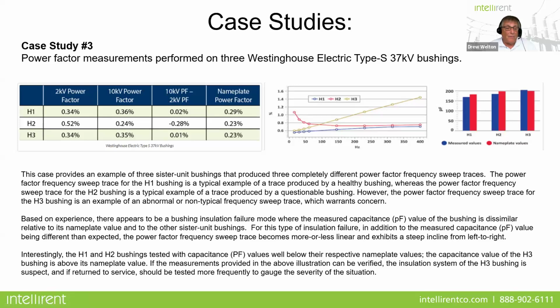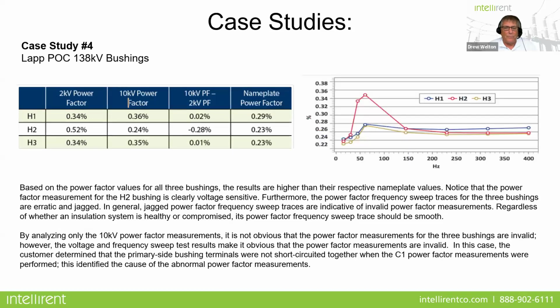So there appears to be a bushing insulation failure mode when measuring the capacitance of a bushing that's dissimilar relative to its nameplate data. And remember what I said: you want to see on good, healthy bushings all three appearing the same. But interestingly, H1 and H2 tested with capacitance values well below their respective nameplate values, while the capacitance value of the H3 bushing is above its nameplate value. So if the measurements provided in the illustration can be verified, meaning did I do the test properly, the insulation system of the H3 bushing is definitely suspect, and if returned to service it should be investigated further.